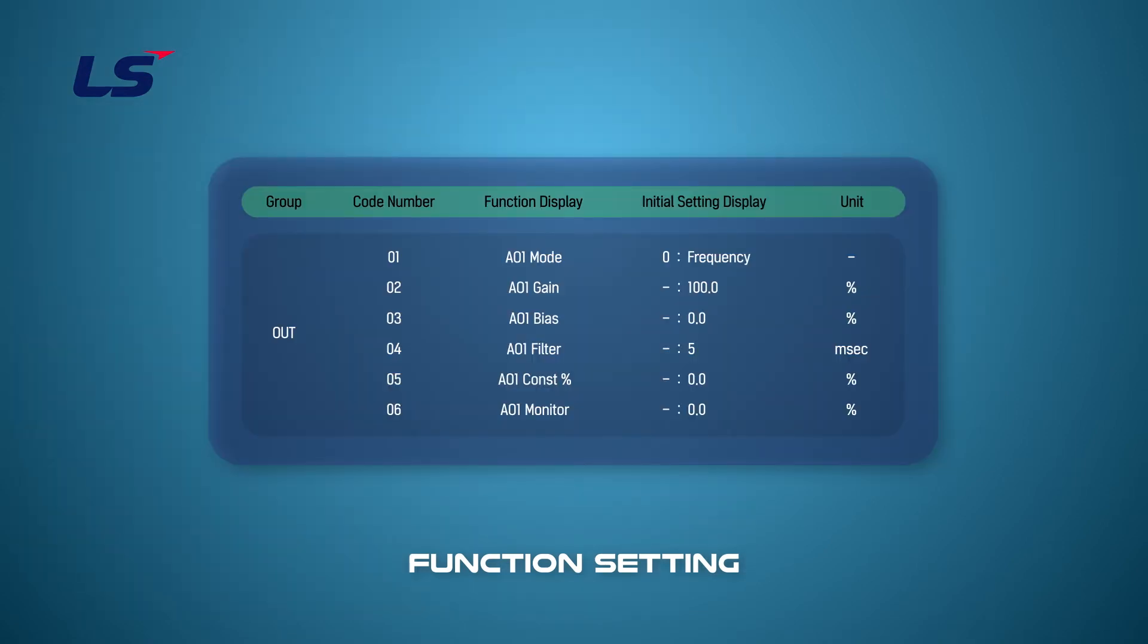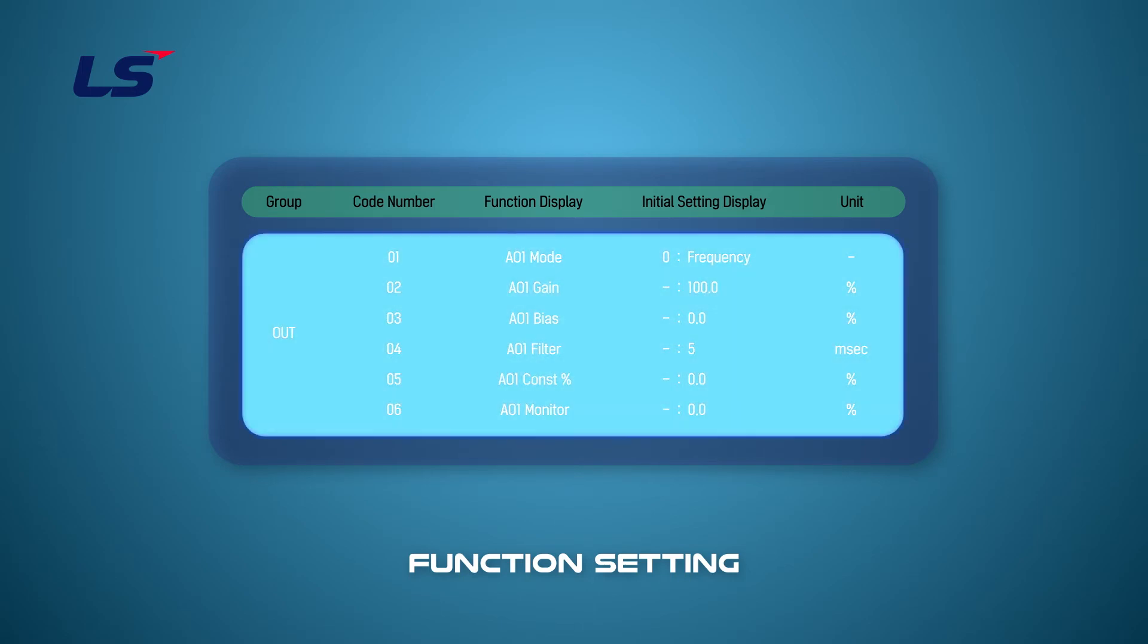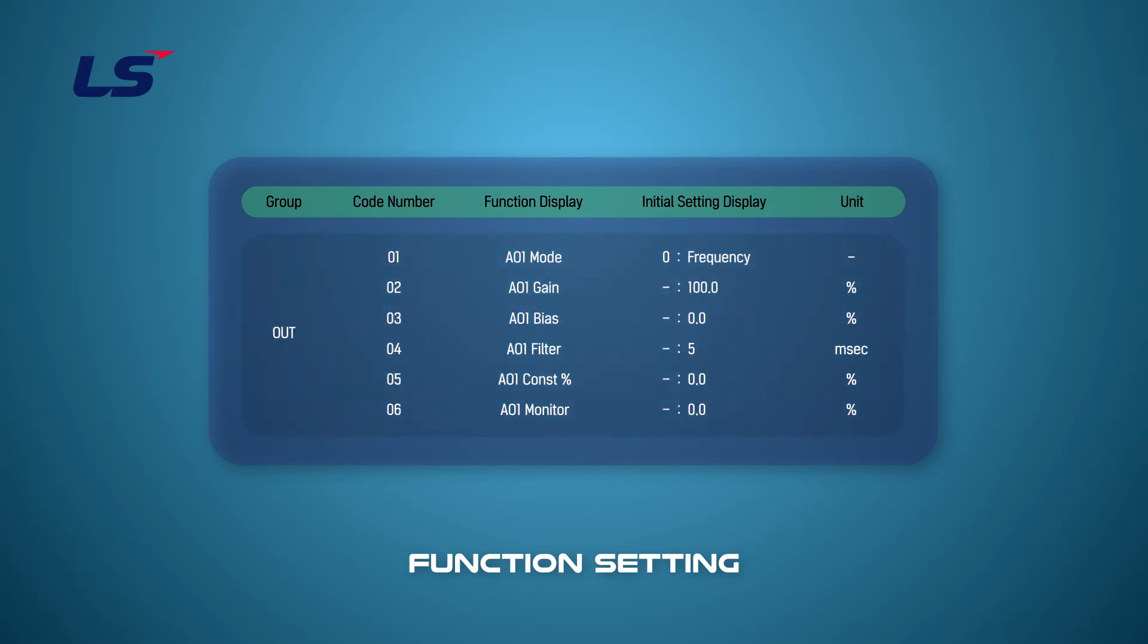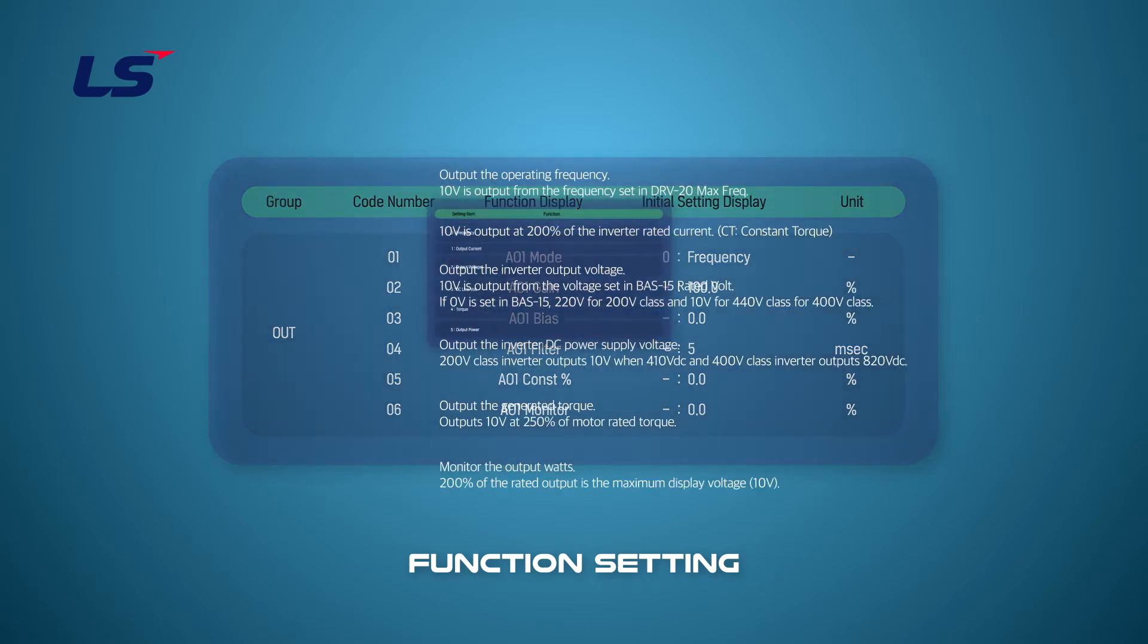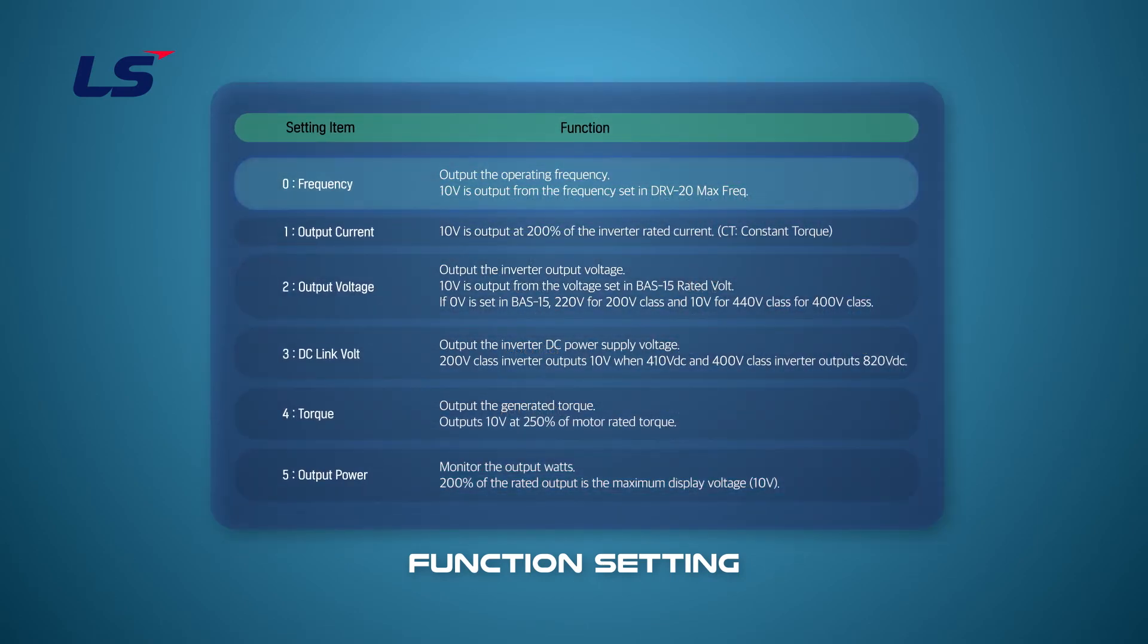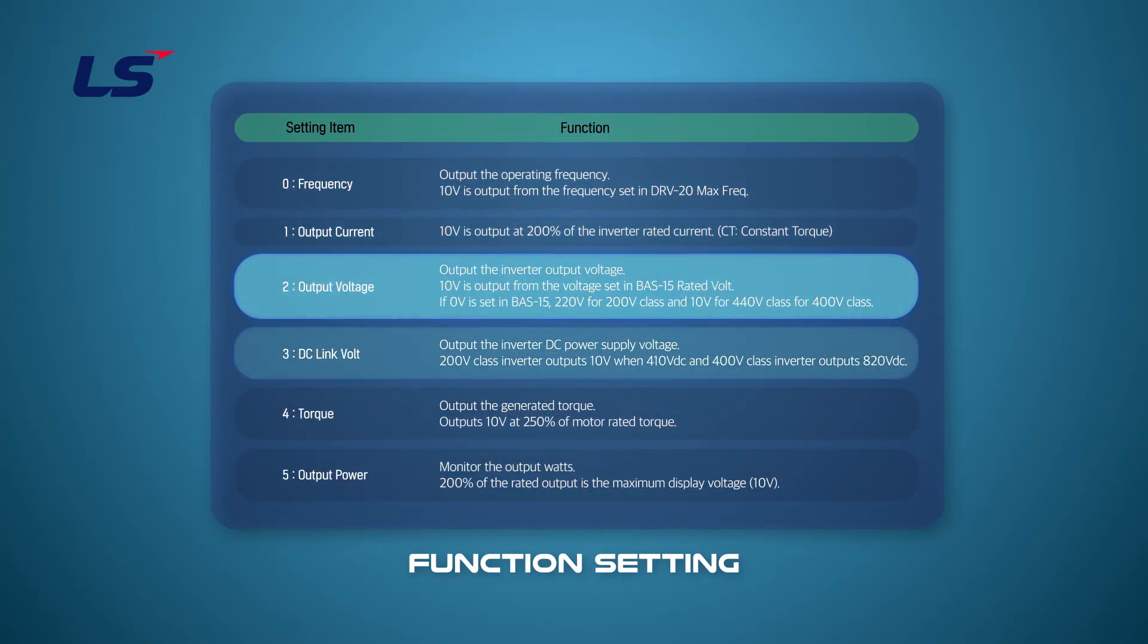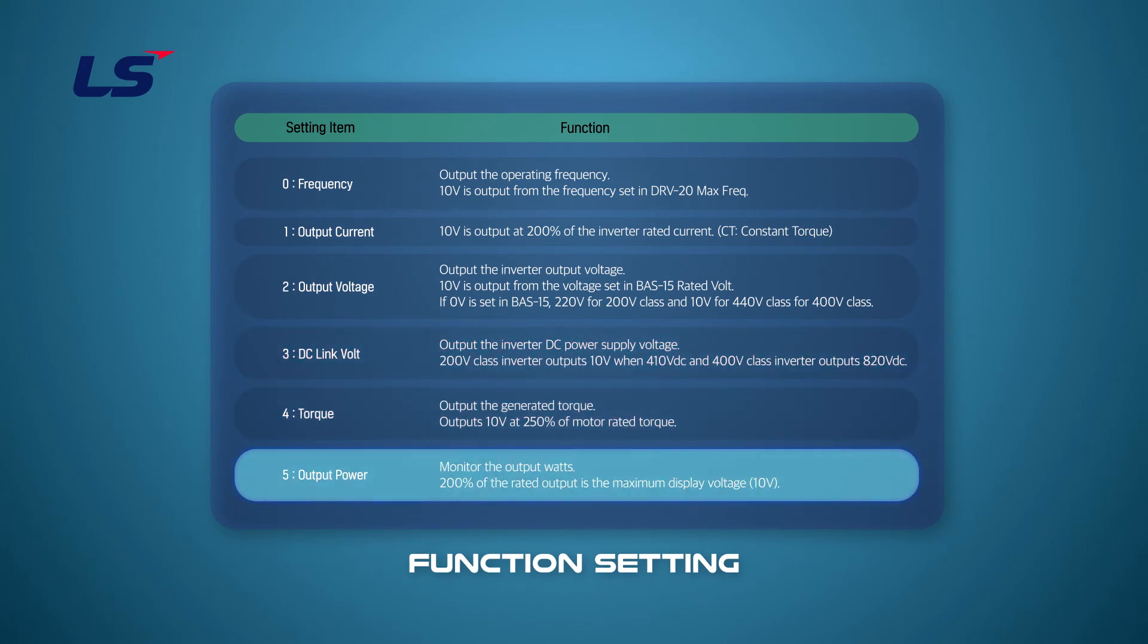Parameters for analog outputs can be set in the OUT group. The AO1 and AO2 terminals are the multi-function output terminals. Therefore, you can select an output item for AO1 directly in parameter OUT group 1. You can select the output item from the driving frequency shown on the screen to the fixed values like output. In this video, we will select the frequency at 0.